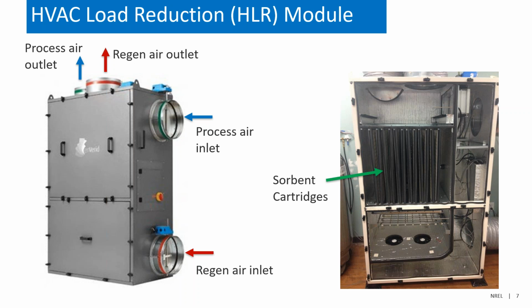And you have process air coming in, it goes through those sorbent cartridges, removes the gaseous contaminants, and then the process air is then delivered to the building. And then during regeneration mode, those dampers are closed off, and you bring in the regeneration air. Well, actually, first what they do is they heat up the sorbent cartridges to release the gaseous contaminants, and then they flush it out through this regen air outlet and flush that to the exterior outside of the building.